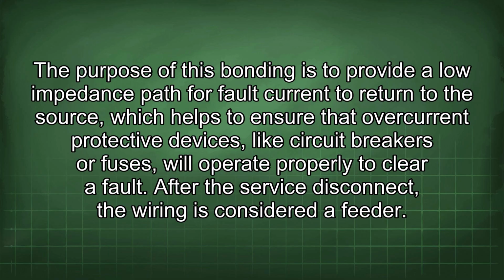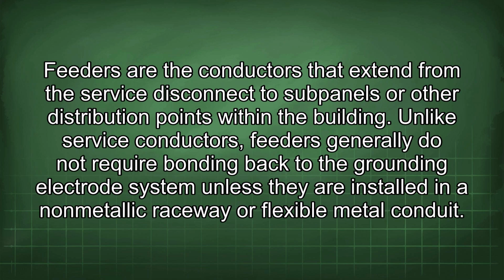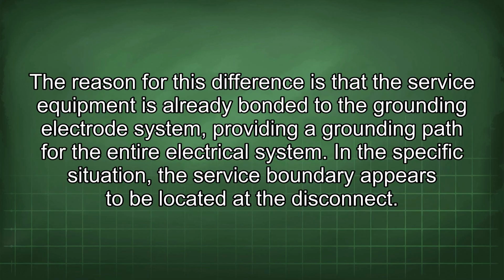After the service disconnect, the wiring is considered a feeder. Feeders are the conductors that extend from the service disconnect to subpanels or other distribution points within the building. Unlike service conductors, feeders generally do not require bonding back to the grounding electrode system unless they are installed in a non-metallic raceway or flexible metal conduit. The reason for this difference is that the service equipment is already bonded to the grounding electrode system, providing a grounding path for the entire electrical system.